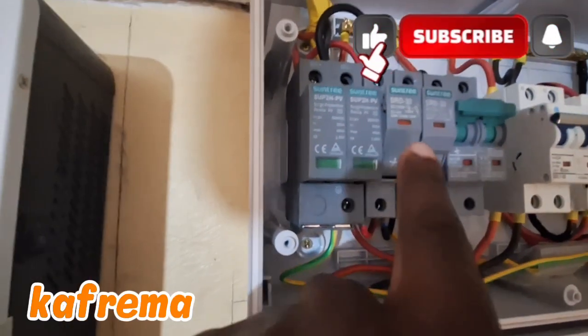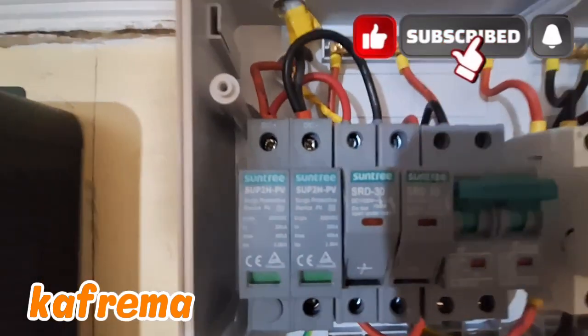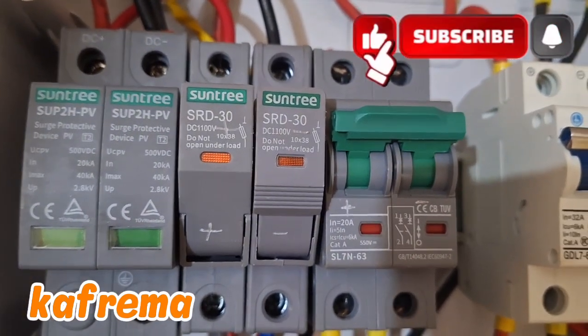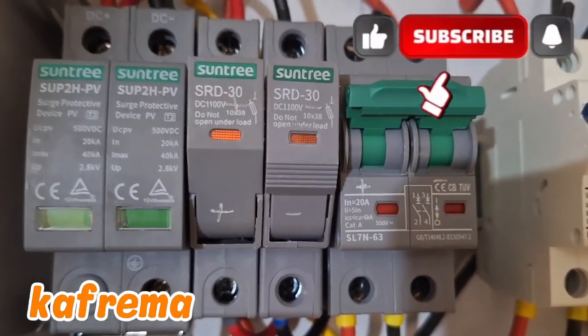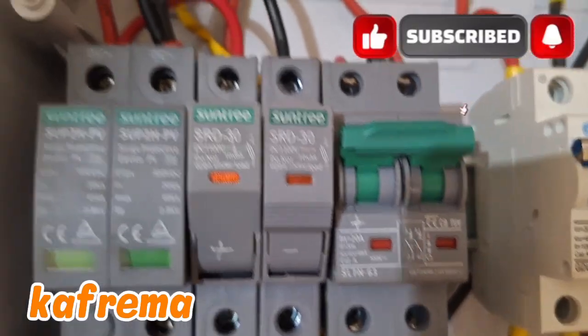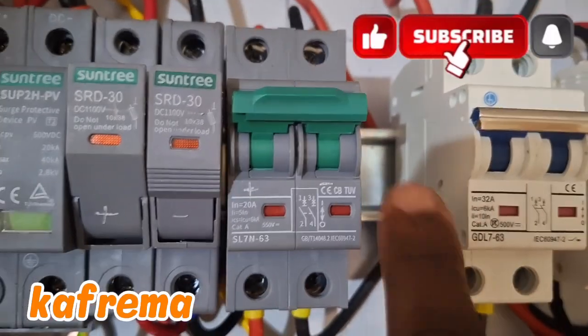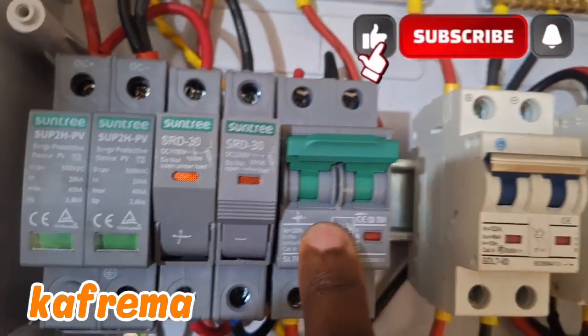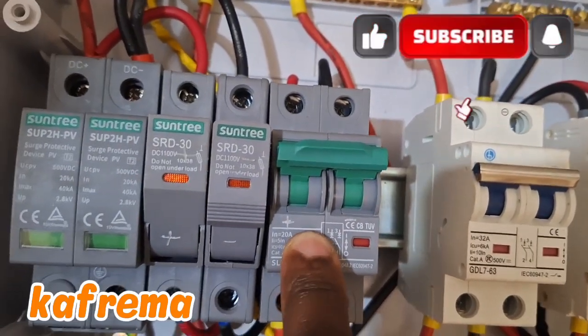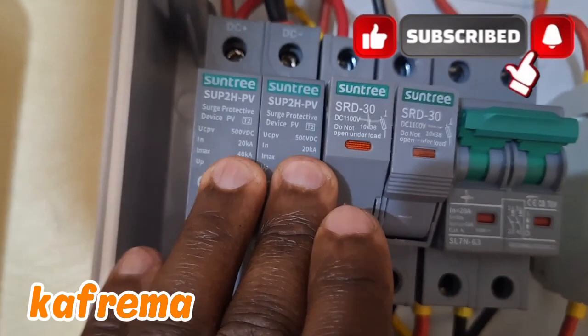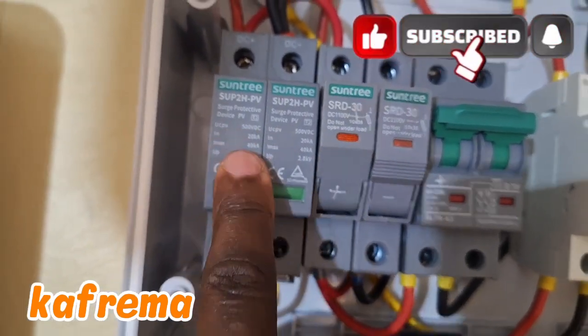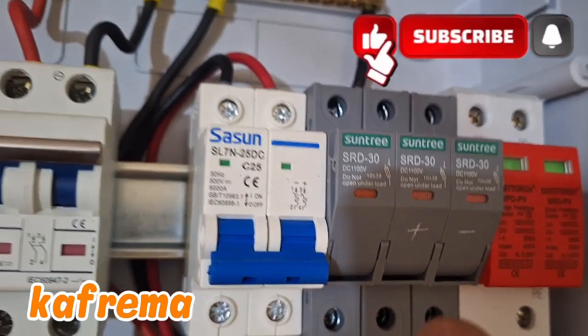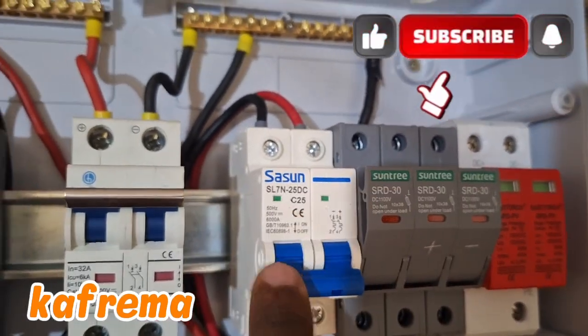Here is earth. Also we have two fuses. With these fuses, you can choose the correct one. Right now, these ones are 30 amperes each. You can calculate the current coming from your solar panels to know the size. Also, you have a circuit breaker. This is a circuit breaker. This is a circuit breaker. This is one array, which is panels connected in series. Also, this is another array. This one is not connected, that's why it is off.